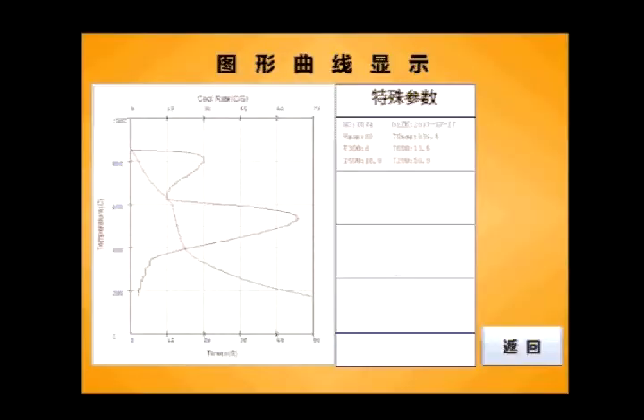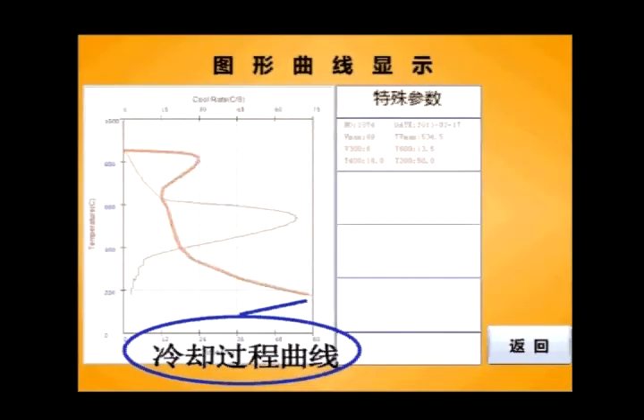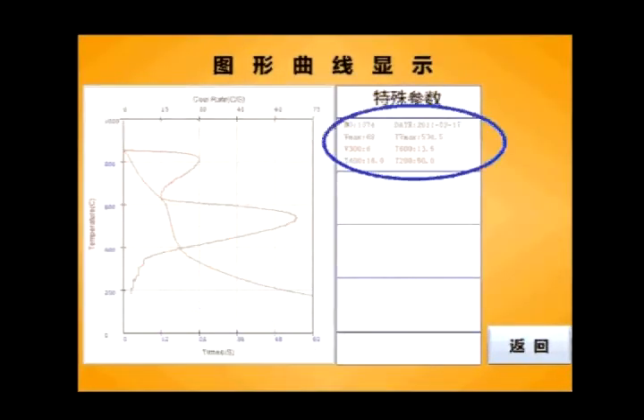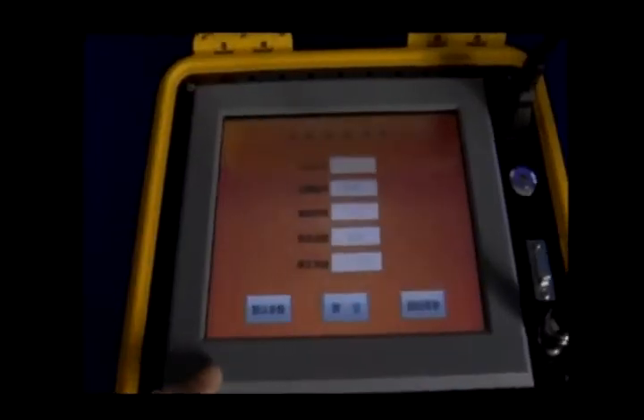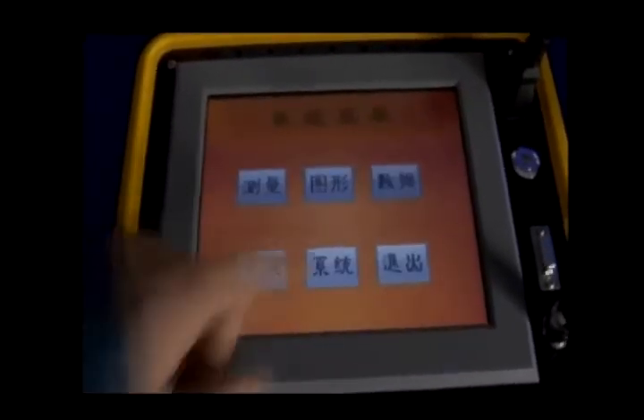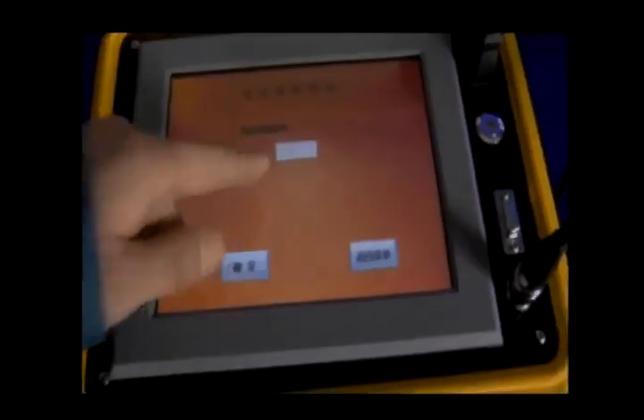The recording device will beep when the test is completed. At the same time, the monitor screen of the recording device turns into a graphic curve. This curve is the result of this test. The result consists of the cooling curve, the cooling characteristic curve, and 6 other feature data. These results are saved in the number you chose before the test. You can select the number to query later.